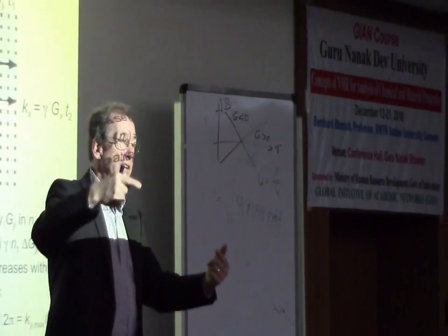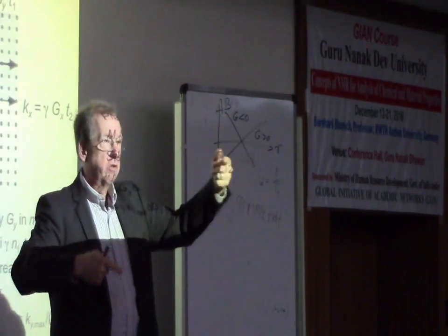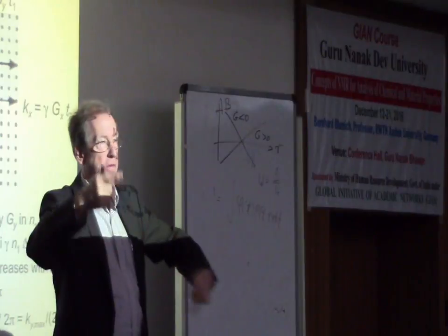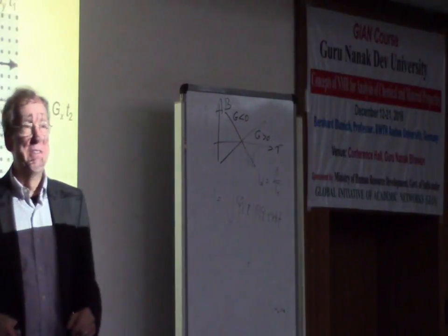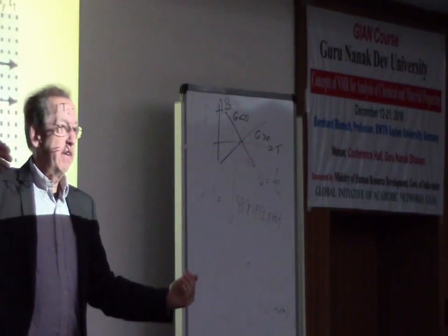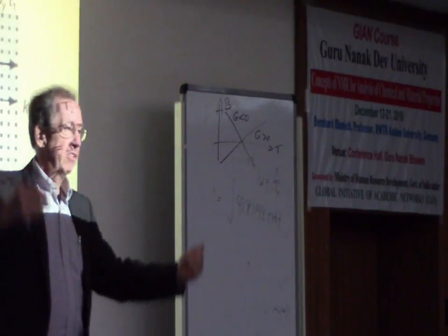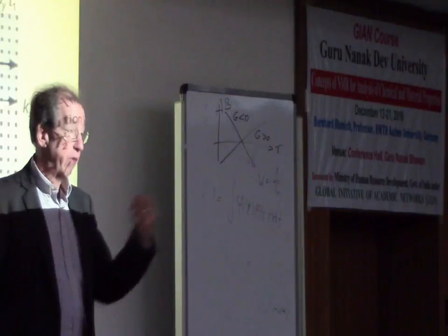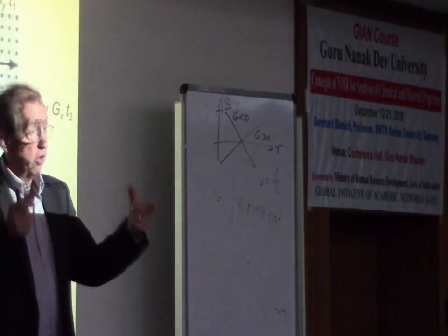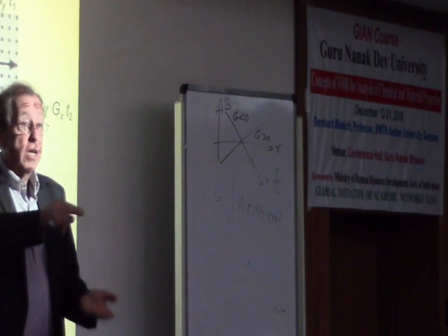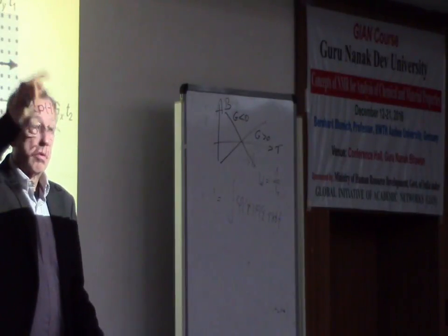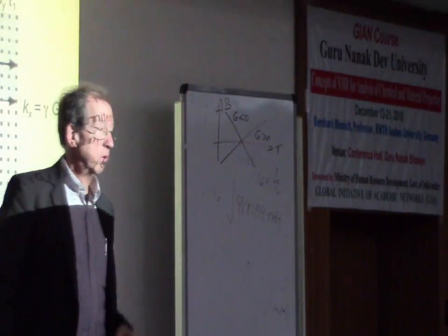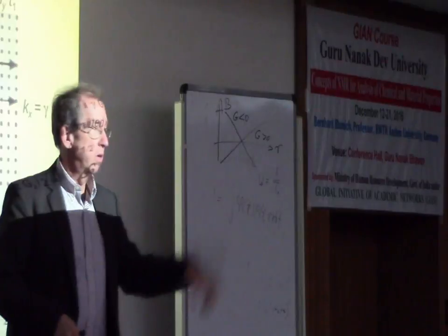And then you get the gradient, and you change the direction, and the other way around, then you get the gradient in the other direction. So the field varies one way or the other way. And that allows you to switch the gradient direction, and the amount of current you throw through the coil gives you the gradient amplitude. So that's something you can do by computer. And you program it on the computer, and then it does it for you.